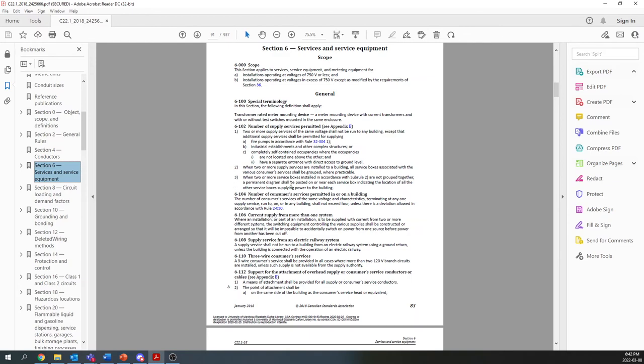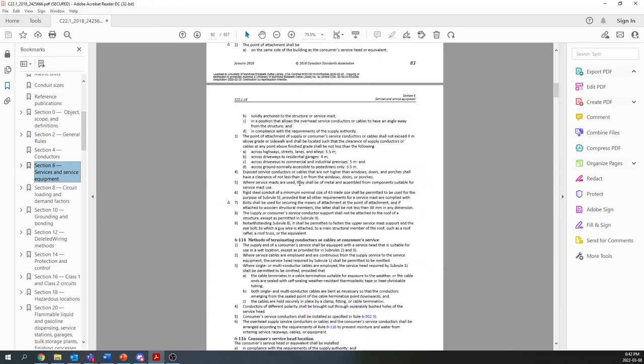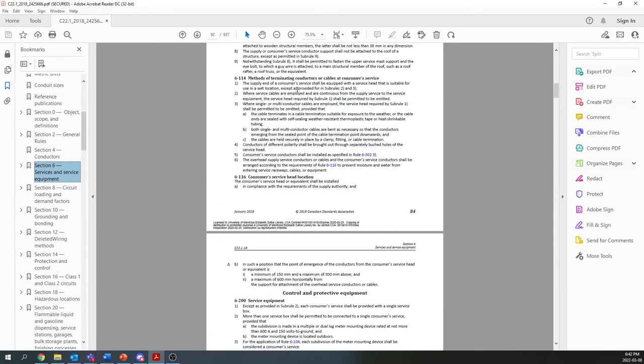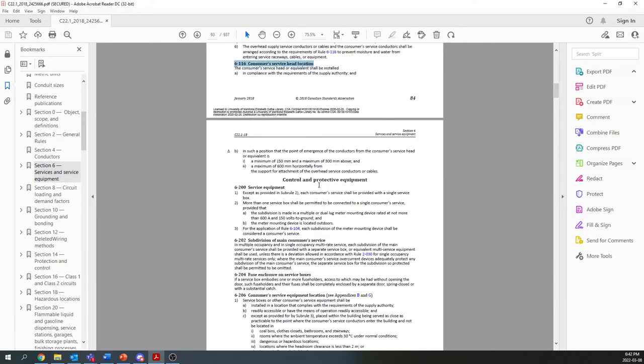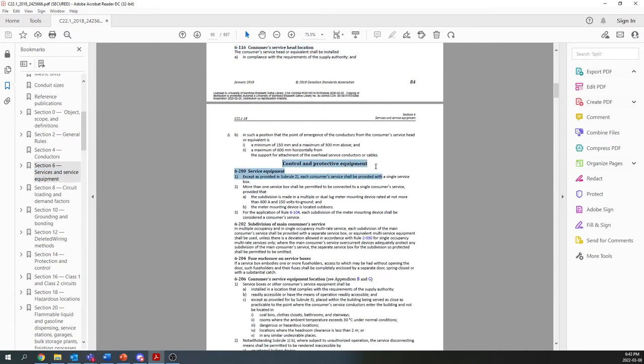So Section 6 is only 7 pages long. It's quite short, but it defines where to put the service head, for example, and the control and protective equipment, what's called the service equipment. The service equipment is your main disconnect, and everything after that disconnect is essentially your consumer's equipment.